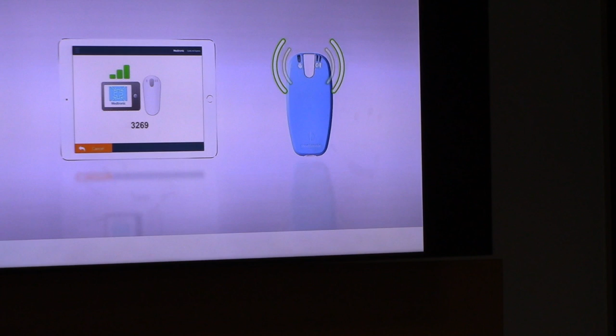And then if you have a high urgency tone, a big beeping means you have to call us at the end of the procedure. And Boston Scientific has a different one: it basically suspends tachytherapy by putting a magnet on. However, they do have a mode which will ignore the magnet. So you want to make sure that that is off in those devices.